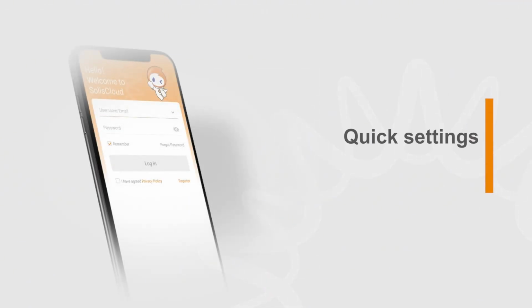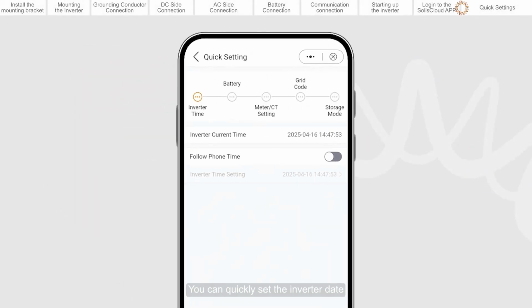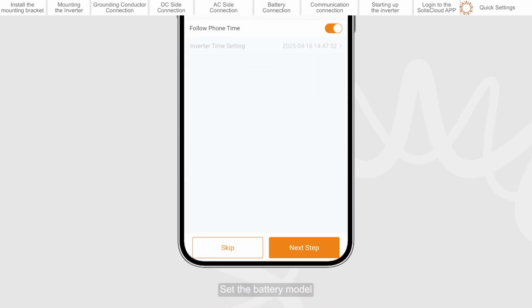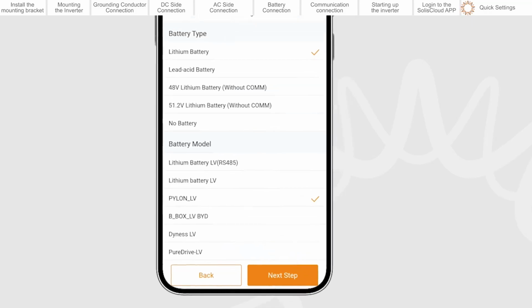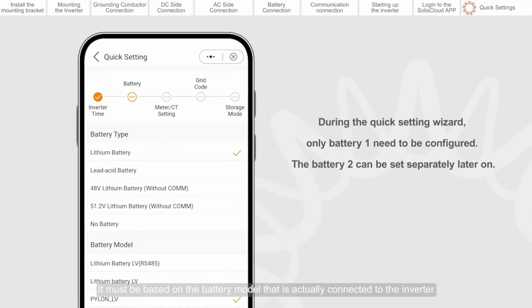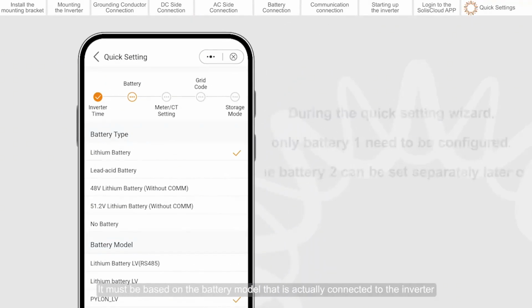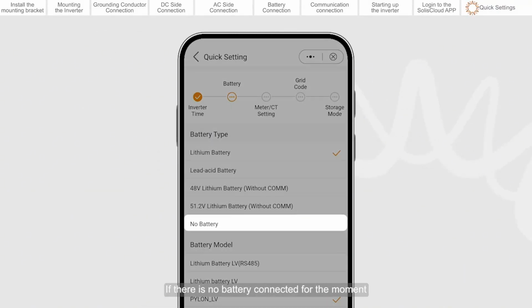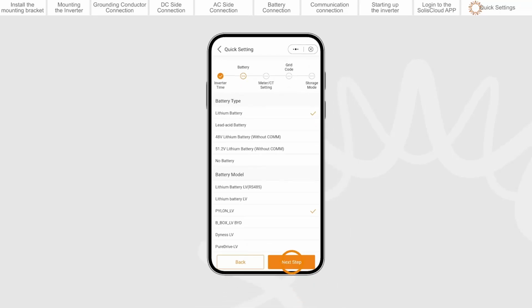Quick settings. You can quickly set the inverter date and time by selecting Follow Phone Time. Set the battery model. It must be based on the battery model that is actually connected to the inverter. If there is no battery connected for the moment, please select no battery to avoid alarms.